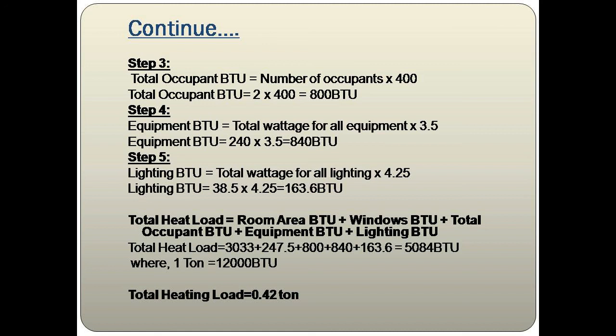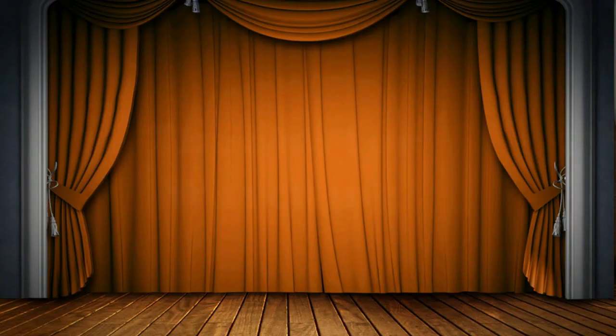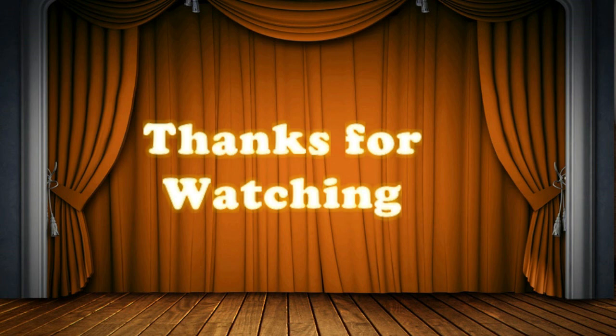Summing all values: 3,033 + 247.5 + 800 + 840 + 163.6 = 5,084 BTU. Since 1 ton = 12,000 BTU, dividing 5,084 by 12,000 gives 0.42 ton of refrigeration. This means a 0.5-ton AC will be sufficient for that room. If a 0.5-ton unit is unavailable, you can go with a 0.75-ton. That's our video for today — please subscribe and leave your feedback in the comments.